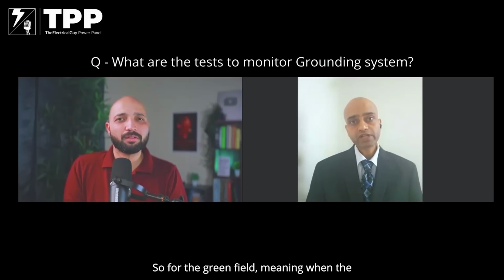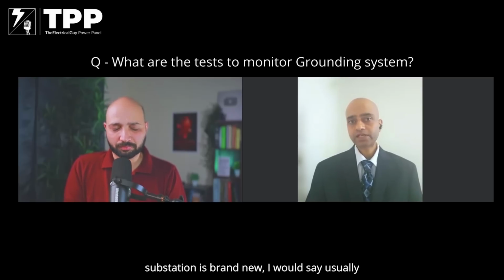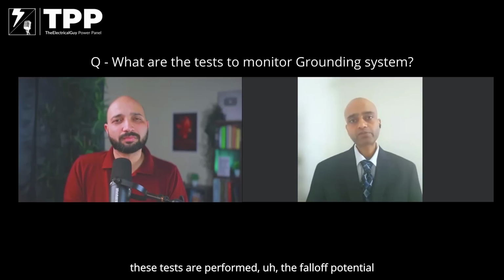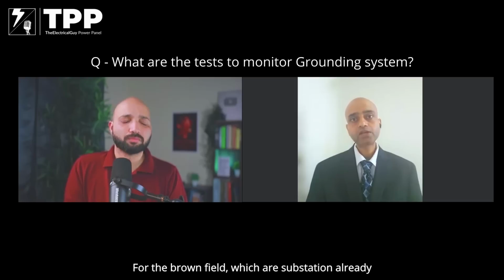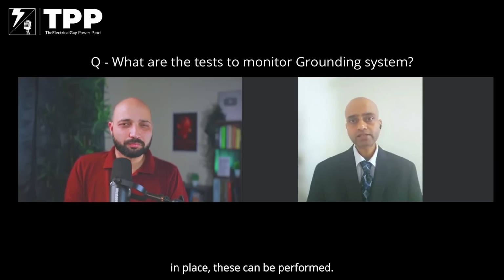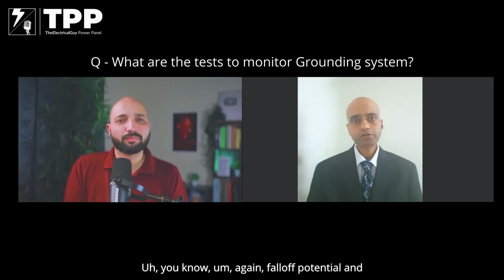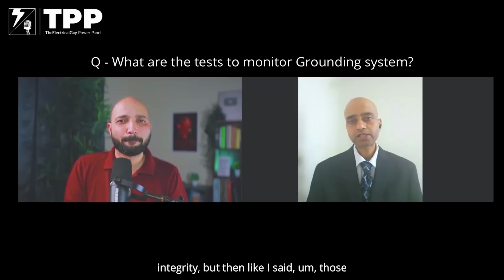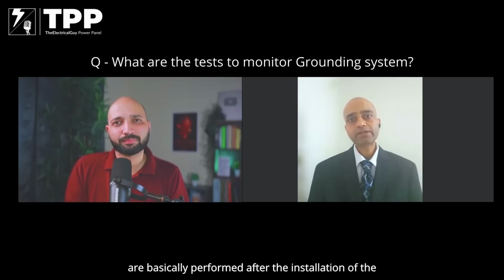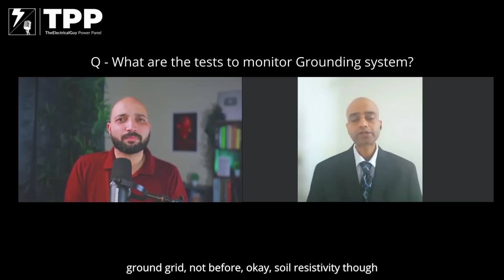So for greenfield, meaning when the substation is brand new, I would say usually these tests are performed - fall of potential is performed before the substation energization. For brownfield, which are substations already in place, these can be performed again - fall of potential and integrity. But those are basically performed after the installation of the ground grid, not before.